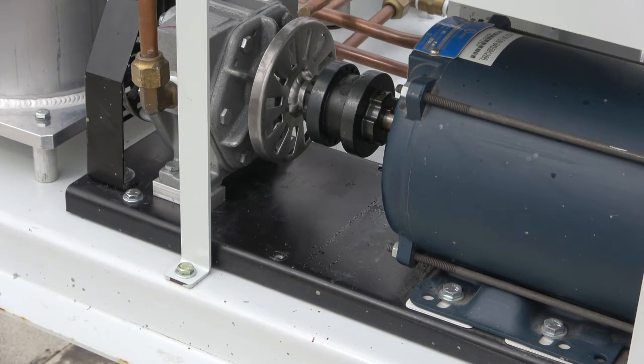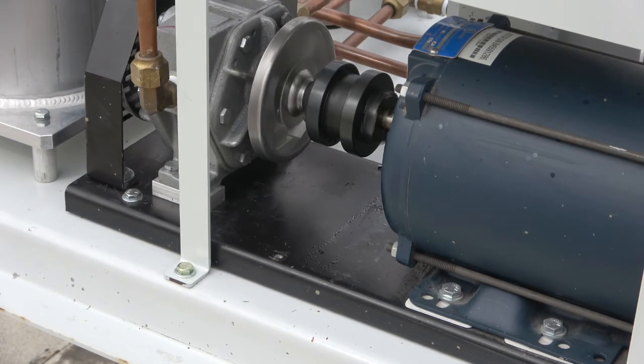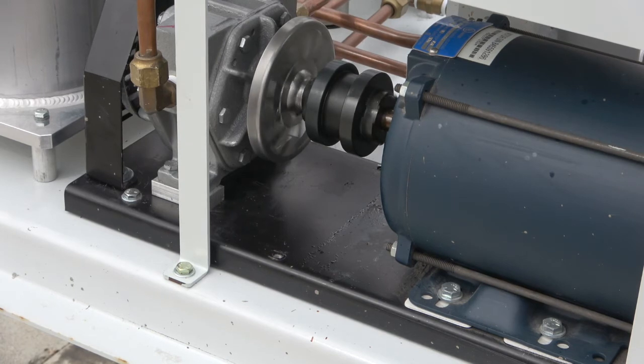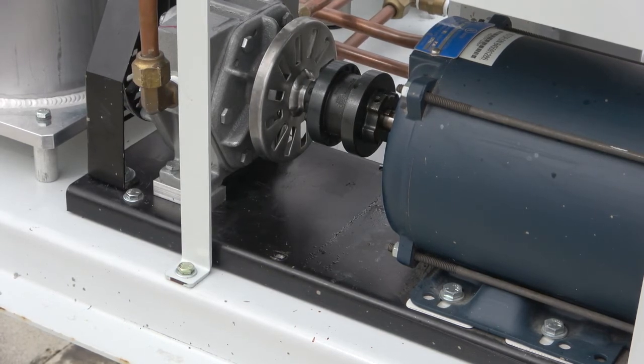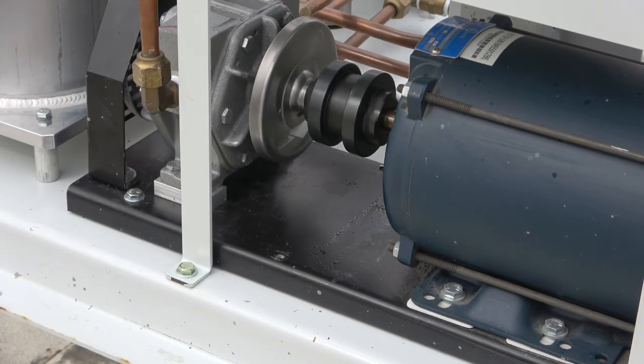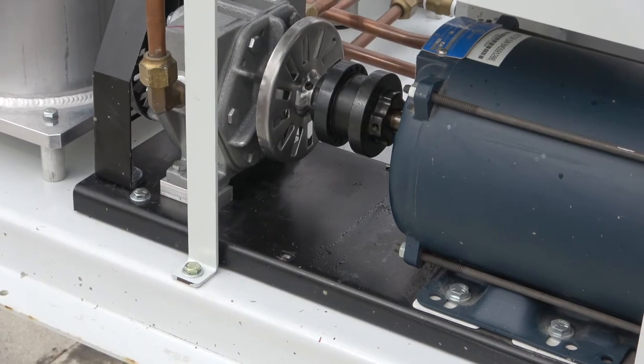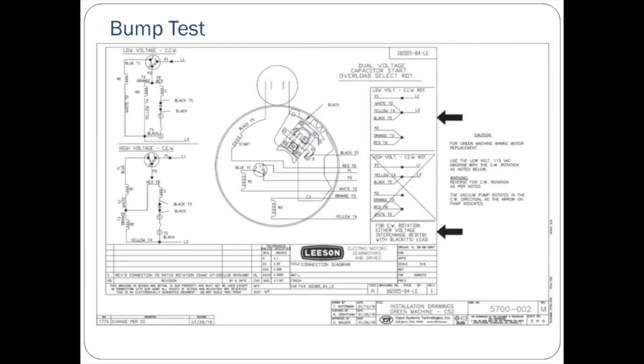Once confirmed, the second person observing the rotation of the pump will see the pump begin to turn for 5 seconds. The desired direction of rotation is noted on the vacuum pump with a sticker. If the pump and motor are turning in the correct direction, the test is completed. However, if the direction of the rotation is incorrect, the polarity of the motor must be switched. This is done by interchanging two wires within the motor junction box. After switching the polarity of the motor, be sure to run the bump test again to verify the pump and the motor are turning in the correct direction.